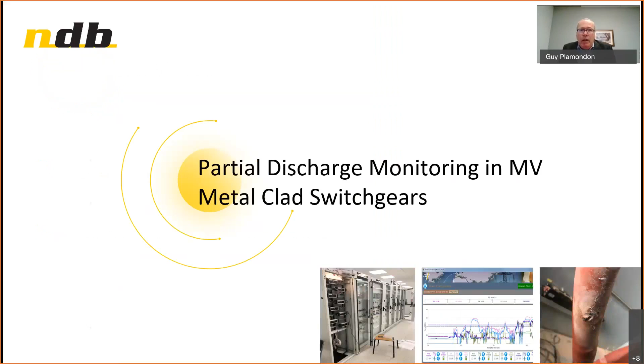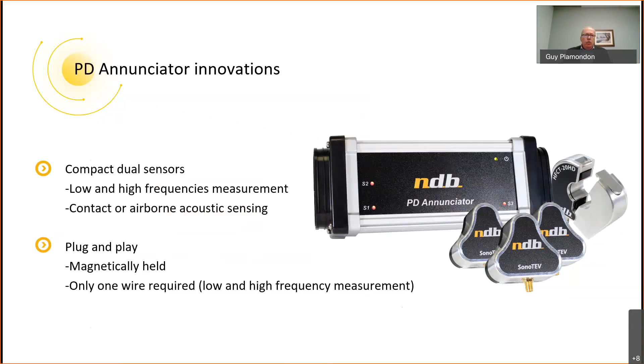We're pretty proud of it. The second technology I want to introduce to you today is a partial discharge monitoring system for medium voltage metal clad switchgears. The innovation here is how compact the device itself and the sensors are. We have a dual sensor that measures low and high frequencies generated by the PD. We do have contact and airborne acoustic sensors, and it's a plug and play system. It can be easily installed on existing and new switchgears.